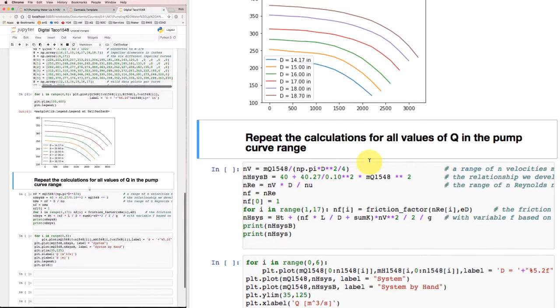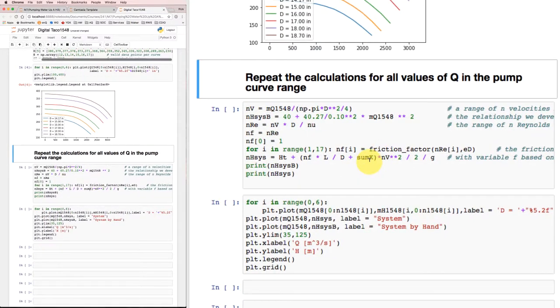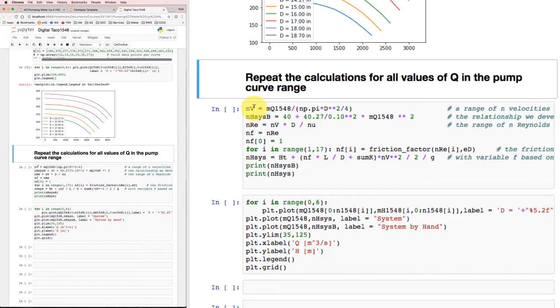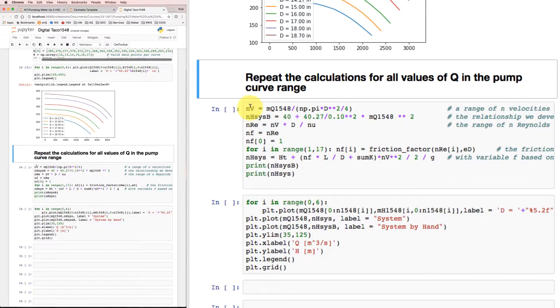So let's repeat the calculations that we did before, but let's do it over all of the values of Q in the pump curve range. I'm going to take an array of different velocities from zero up to whatever the velocity is that corresponds to 3200 US GPM. I'm taking the collection of metric flow rates that the pump can deliver, and I'm dividing by pi d squared over 4 for my pipe. That'll give me a bunch of pipe flow velocities.